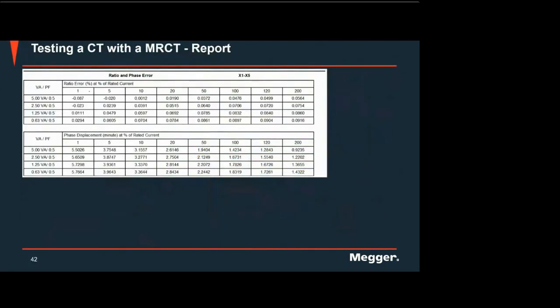And like I've said, you have multiple values of error at different rated current here, at different VA, at different percentages of the rated current, and of course the error here. Now, for example, if you put the actual burden here, maybe 0.7 VA and 0.9 here, then you will have additional information here without doing the test again. Just go to the nameplate setting, add the actual burden, and then you will have the actual accuracy of the CT.